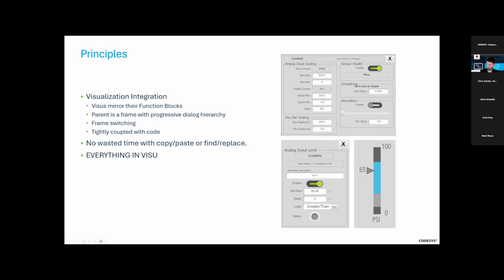We put all of our configuration in the visualization. So you see here, all of the scaling for this sensor is in here. We don't do it in the code. It's adjustable by the user. They can go through and invert a sensor if they need to, set a normally open versus normally closed, move it to a new I/O point, or rename it to whatever they want to call it. This alternate description here for a limit is one of those. If this limit is controlling a pump cut-in value, they can just type that in so it's a little more obvious to them. We try to put everything we can in there.